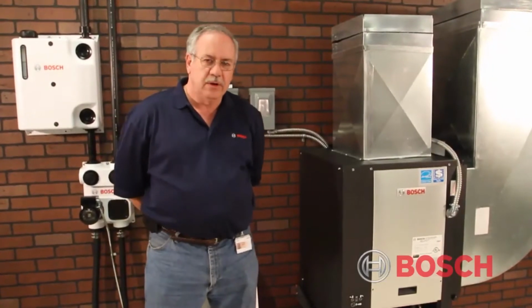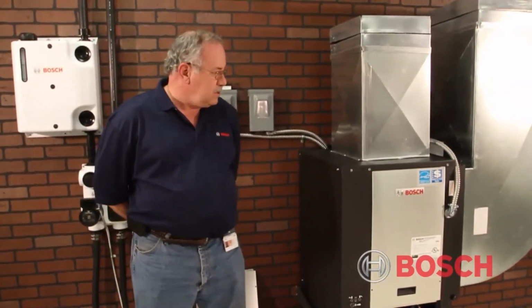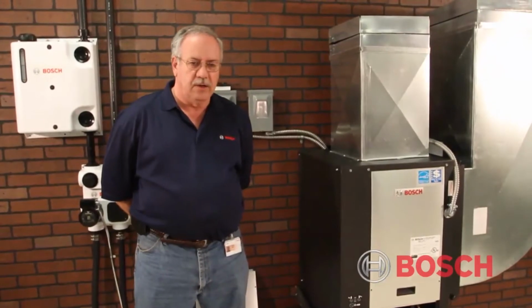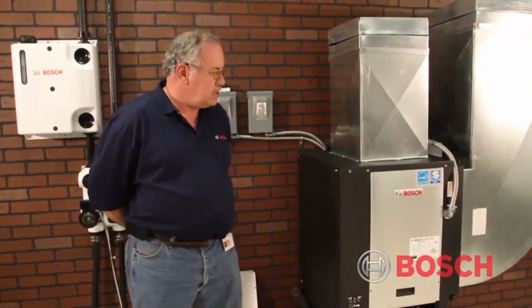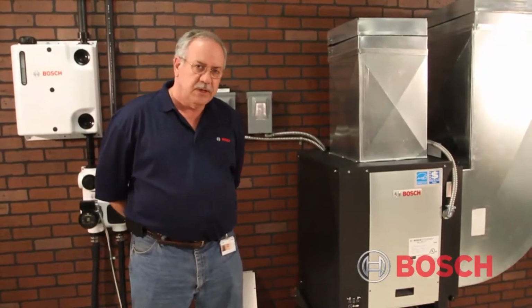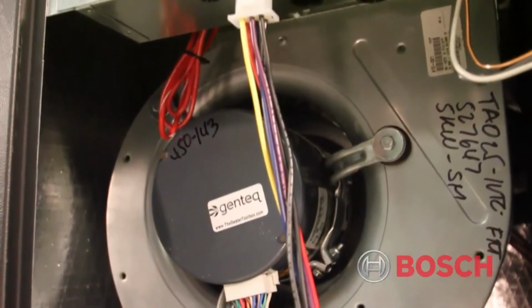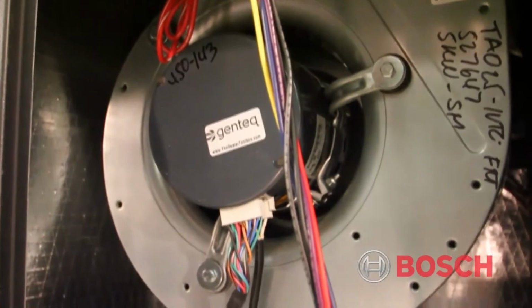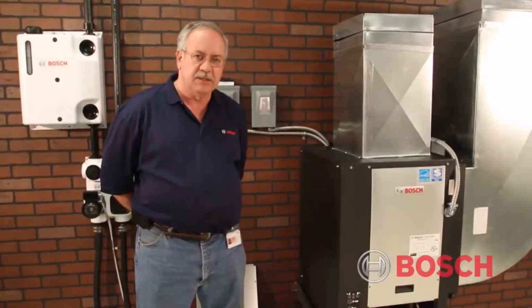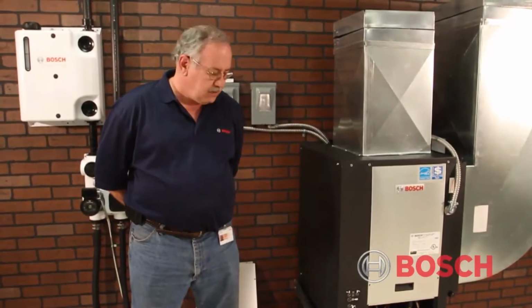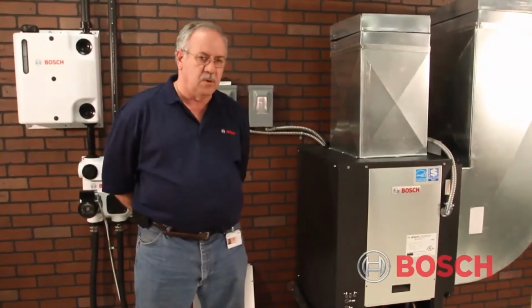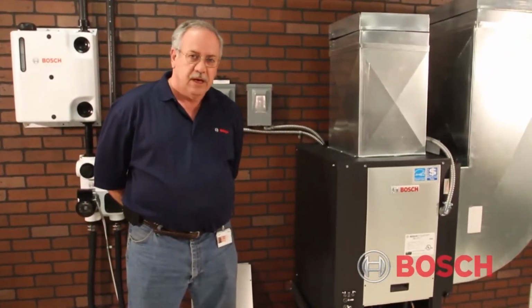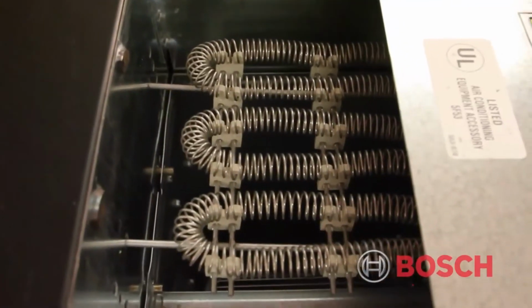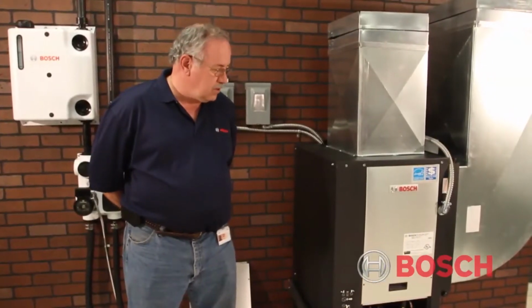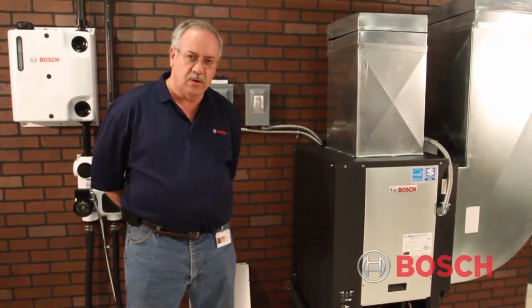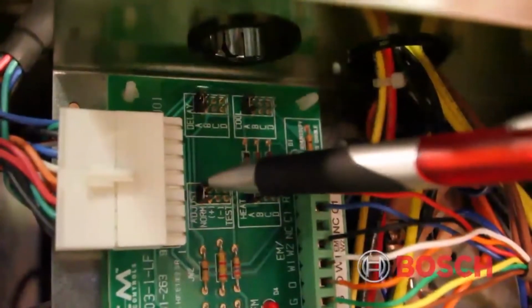Okay, with the TAO25 that we see here, once we've checked everything and it's all installed, we want to do the commissioning. Part of the commissioning involves proper airflow. This particular unit has the electric commutated variable speed drive motor in it that maintains constant CFM against varying pressure. It comes set with the motor control interface board on normal from the factory, and with a heater installed in this unit, we have the choice of going up 15% on that switchboard with a switch or leaving it on normal.